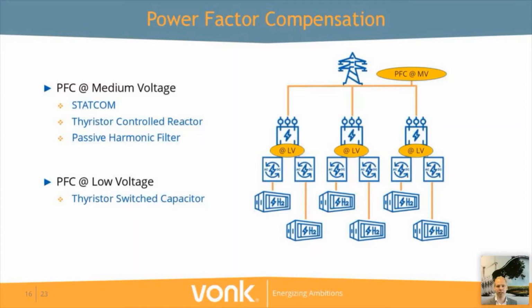STATCOM is limited by the amount of power that it can handle. It depends a bit on the application environment, but mostly you won't get over several tens of megawatts in compensation, or you have to apply more in parallel. And secondly, the second downside of it is that it's quite expensive. The second option is that of a thyristor controlled reactor. In contrast to STATCOM, it can only tackle power factor but no harmonics, and it has a larger footprint compared to STATCOM, but it's cheaper.